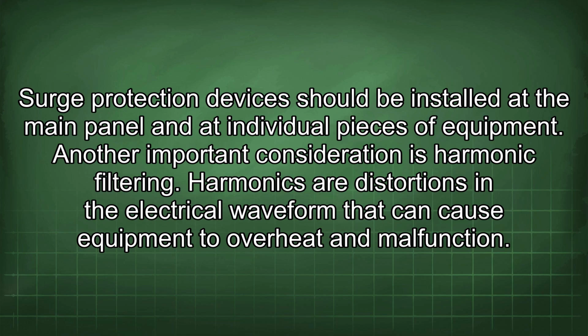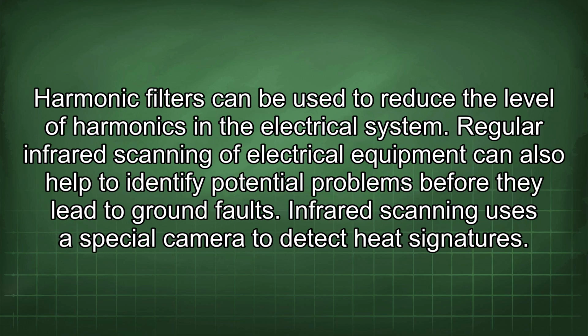Another important consideration is harmonic filtering. Harmonics are distortions in the electrical waveform that can cause equipment to overheat and malfunction. Harmonic filters can be used to reduce the level of harmonics in the electrical system.